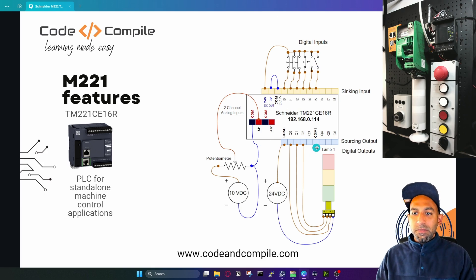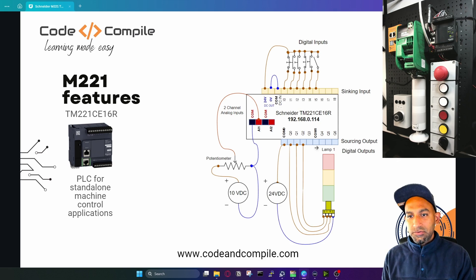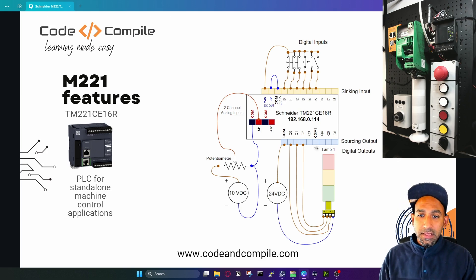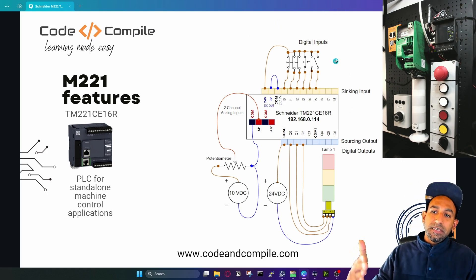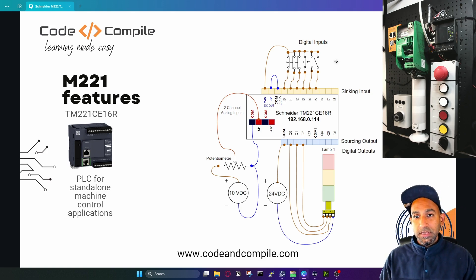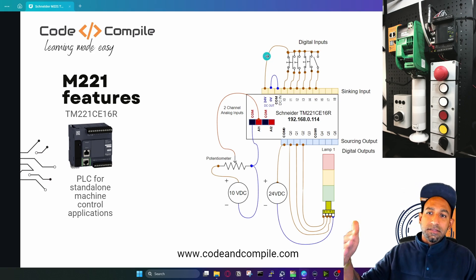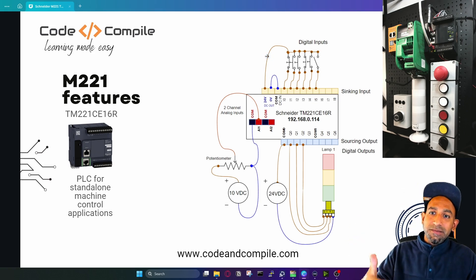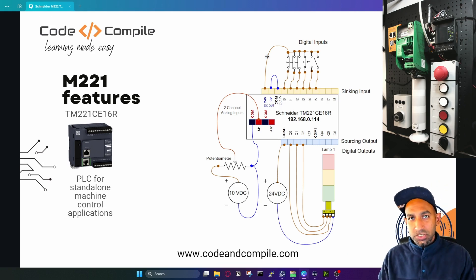If you're familiar with PLC wiring, this is easy. But if this is the first time you're trying to understand how to wire a PLC, let me give you a brief overview. On the top side we have digital inputs — digital inputs are the ones that give signals to the PLC. Signals could be 24 volt or zero volt. Here we have a sinking input type of wiring. With sinking input, the signals you connect to the PLC supply 24 volts, and the PLC sinks that signal.